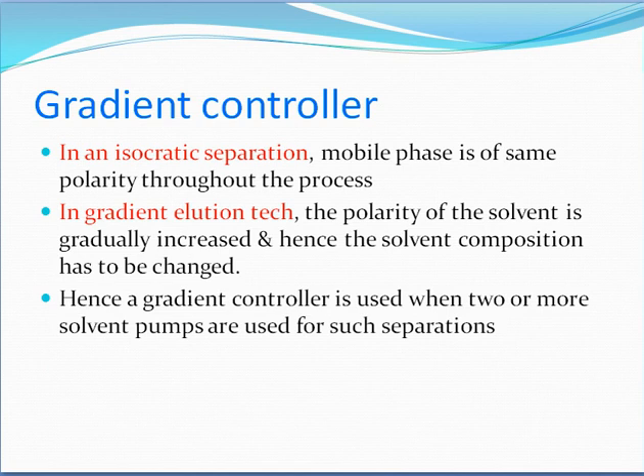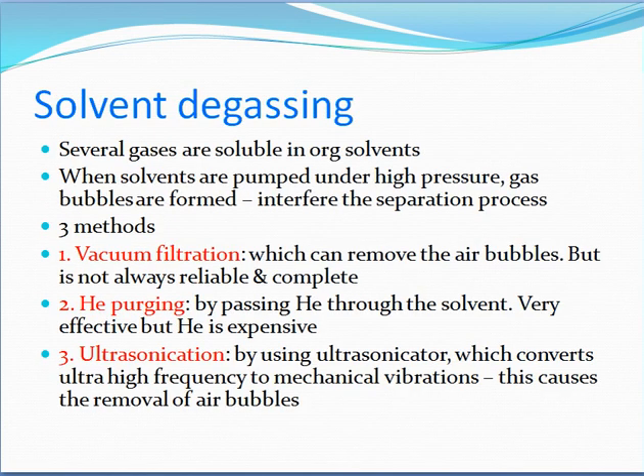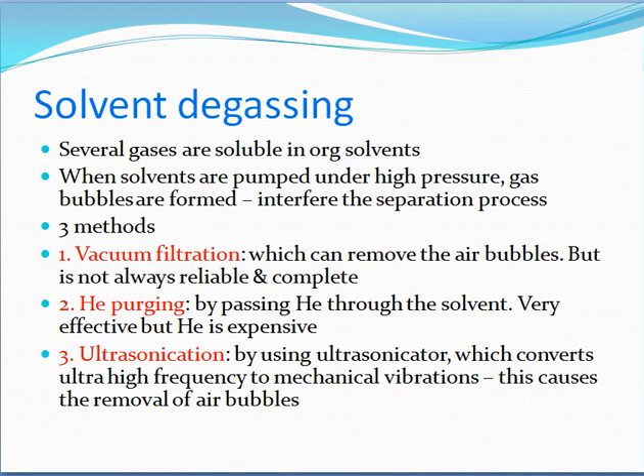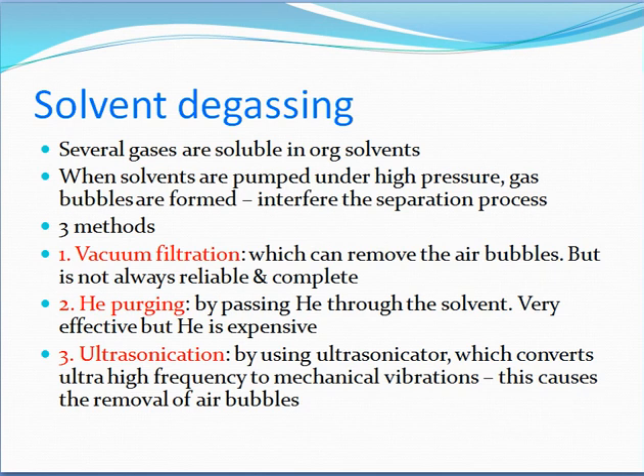Solvent degassing is necessary because several gases are soluble in organic solvents, and when solvents are pumped under high pressure, gas bubbles form and interfere with the separation process. Three major degassing methods are used: vacuum filtration, helium purging, and ultrasonication. Vacuum filtration can remove air bubbles but is not always reliable or complete. Purging by passing helium through the solvent is very effective but expensive. Ultrasonication uses an ultrasonicator to convert high-frequency energy into mechanical vibration, causing removal of air bubbles.